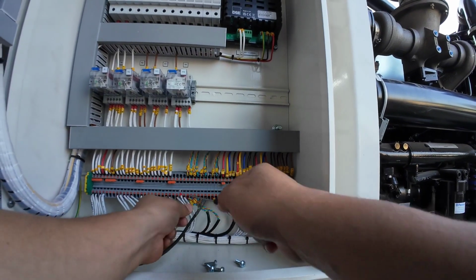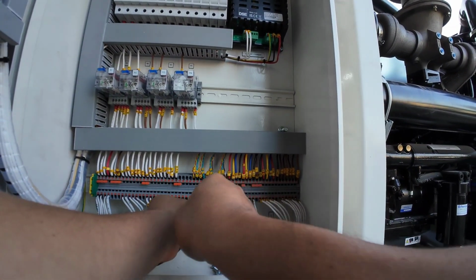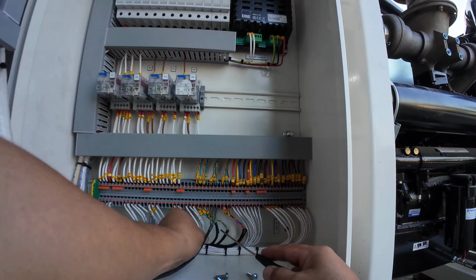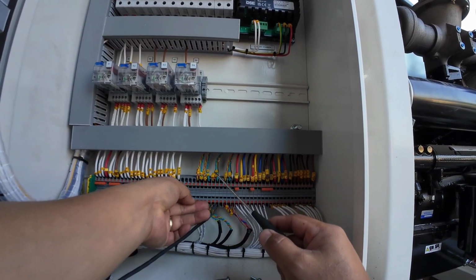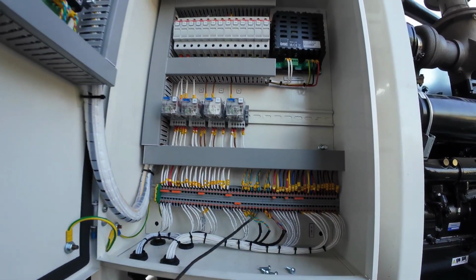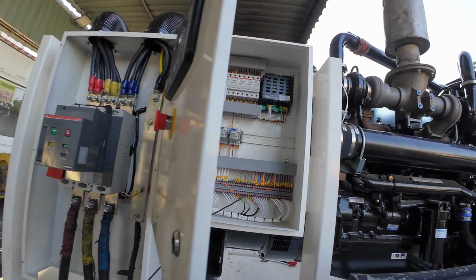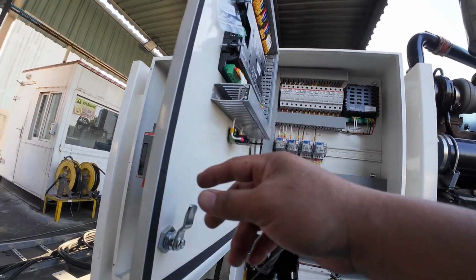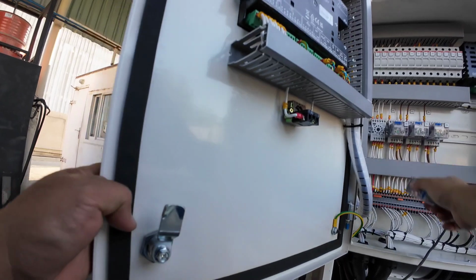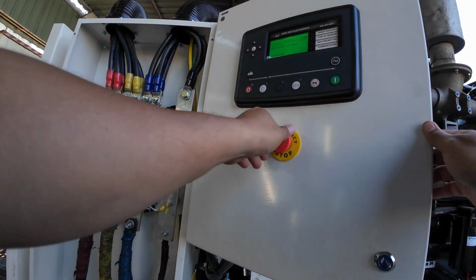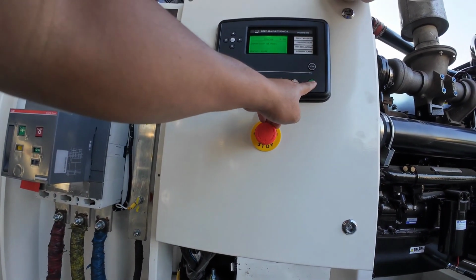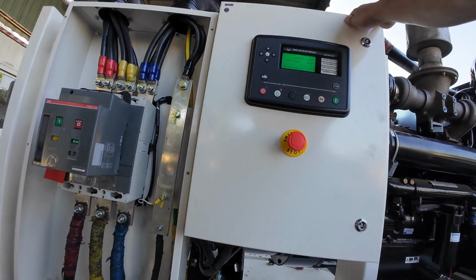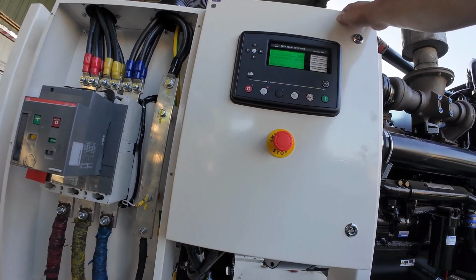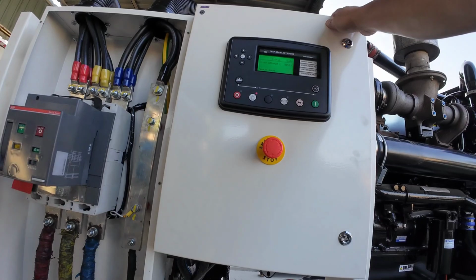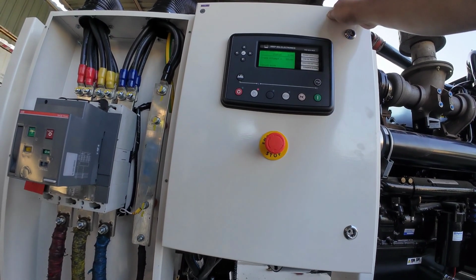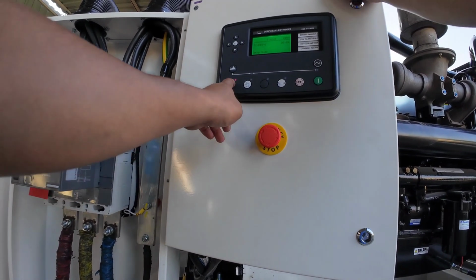Once we start the generator, we have full control and full adjustment for automatic functions, and even if you want to adjust manually through the controller, you can. For now I am going to start the generator first and check if we have a problem or any alarms.